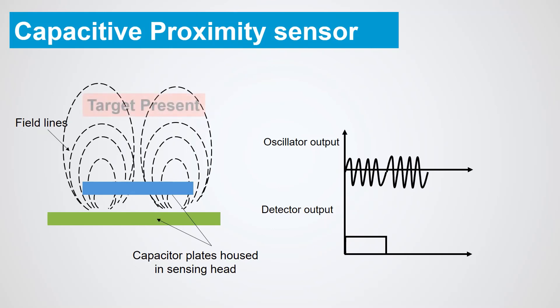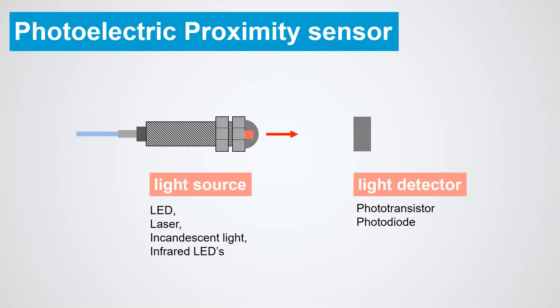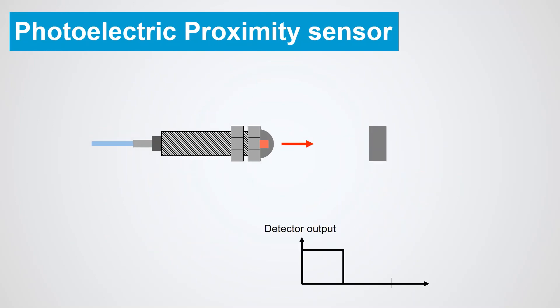Note the difference between inductive and capacitive sensors: inductive sensors oscillate when the target is absent, and capacitive sensors oscillate when the target is present. Photoelectric proximity sensors use a beam of light to detect the presence of objects that block or reflect the light beam. A beam of light passes from the light source and a phototransistor detects the presence or absence of light from the source. Incandescent light or infrared LEDs may be used as a light source.